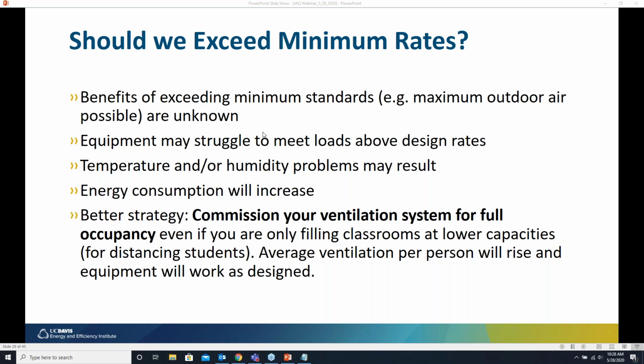So I would recommend instead to commission your ventilation systems for your classrooms for full occupancy. Say that that classroom normally holds 34 people. Commission it to provide enough ventilation, or 500 CFM for those people. And then I'm seeing suggestions that classrooms may be filled at lower capacities, and so to distance students. And in that case, you'll actually be providing more CFM per student. You can also encourage teachers to open doors and windows in addition to using mechanical ventilation when outdoor conditions are favorable and it's safe to do so. And then that will increase the overall total ventilation at times as well.